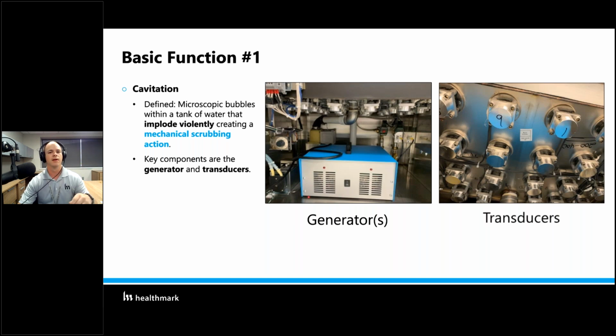I will say, just as a general thing to be aware of, I'm seeing another function being added to some ultrasonic cleaners now, which would be thermal disinfection. Thermal disinfection is just a low-level disinfecting cycle with hot water, all right? But if your ultrasonic cleaner is equipped with that, then you have to understand that, one, your cycle times will probably be a little bit longer, and number two, there's probably an onboard heating element in the ultrasonic cleaner that could also fail. So you would want to test your water temperature to make sure that it actually reaches that thermal disinfection level. So that's just something to be aware of. That is kind of something that I'm seeing more and more of. But for the purposes of this specific presentation, I wanted to dig in more with this function number 3, this soil removal from within lumens. And as we go, you'll kind of understand more why I wanted to dig into this one specifically.